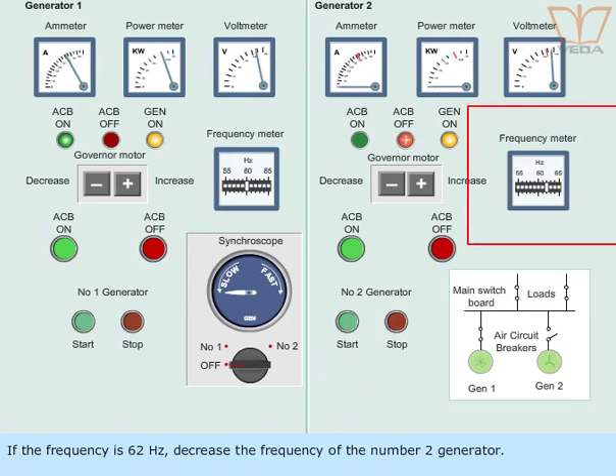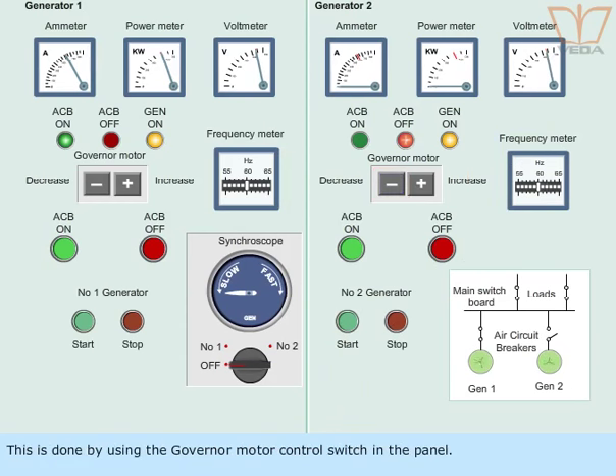If the frequency is 62 Hz, decrease the frequency of the number 2 generator. This is done by using the governor motor control switch in the panel. This decreases or increases the speed and hence the frequency of the generator 2.